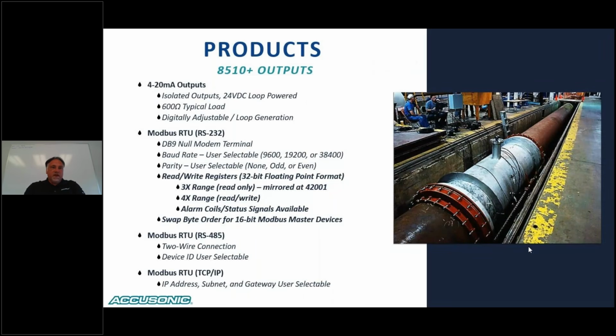Diving a little more into the outputs, again, we provide the unit with 4 to 20 milliamp outputs. They are isolated, so we power the 24 volt DC loop. 600 ohms is a typical load. The nice thing about these 4 to 20 outputs is they can be digitally adjusted, meaning you can digitally trim them to 4.00 and 20.00 milliamps to avoid any type of offsets in your outputs. For Modbus, it is RTU.